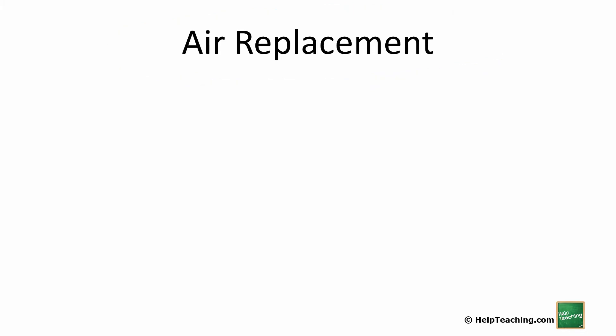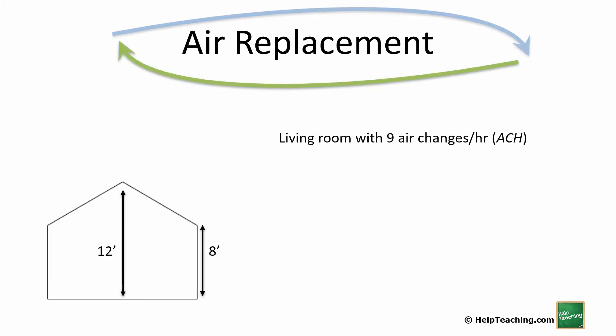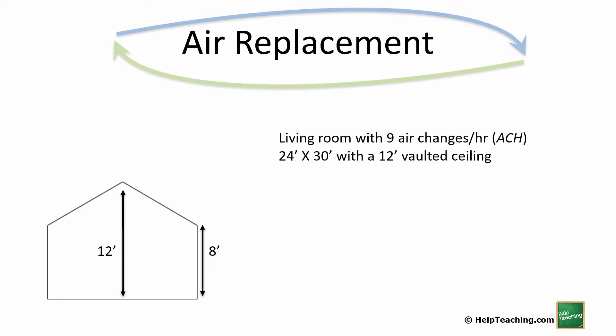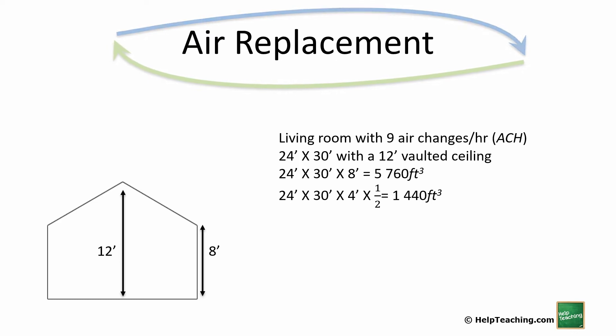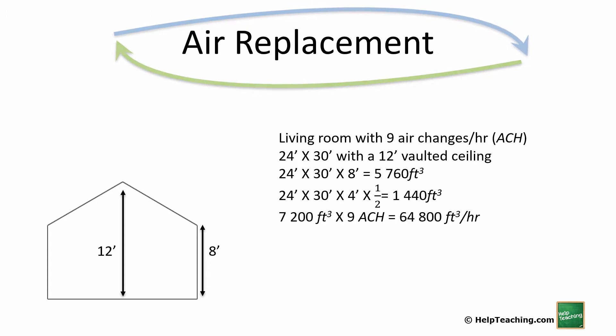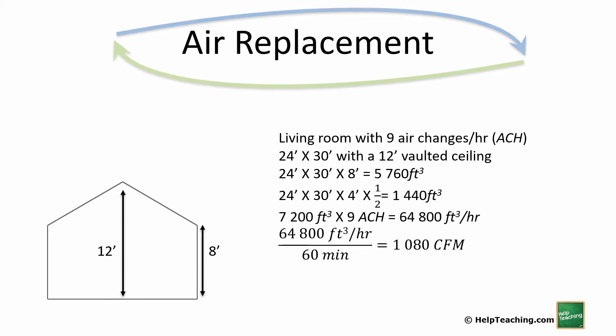Next is a living room with 9 air changes per hour. The room is 24 by 30 feet with a 12-foot vaulted ceiling, meaning it is open to the peak of the roof. First we calculate the bottom 8 feet as a rectangular prism: 24 times 30 times 8 equals 5,760 cubic feet. Then we handle the vaulted triangular piece at the top — same area but 4 feet high (since 8 plus 4 equals 12), divided by 2 as it's a triangle, giving 1,440 cubic feet. Adding the two together gives 7,200 cubic feet. Nine air changes gives 64,800 cubic feet per hour, and dividing by 60 gives 1,080 cubic feet per minute.